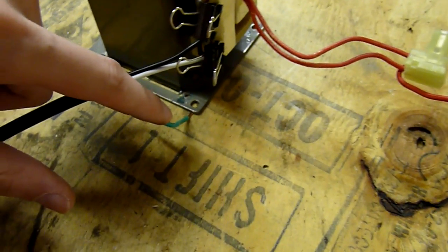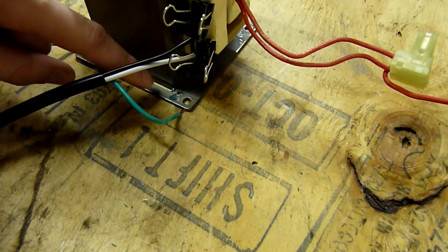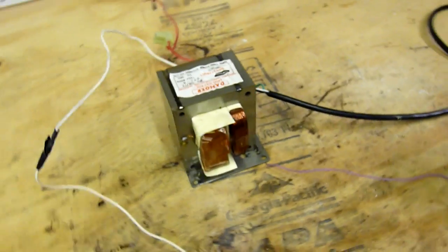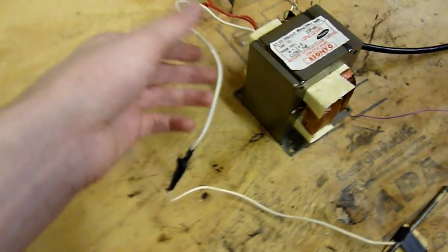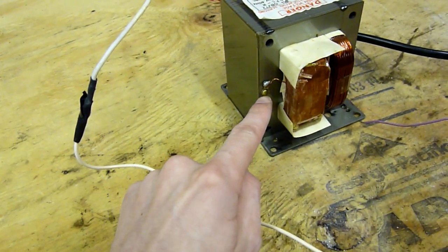And then, of course, the way this is wired, the safety ground goes to the case of the transformer. And if you look, you'll notice this is the high voltage lead right here. It comes off the primary, or the secondary. And the other side of the secondary is tied right to the case of the transformer, right to the big core.